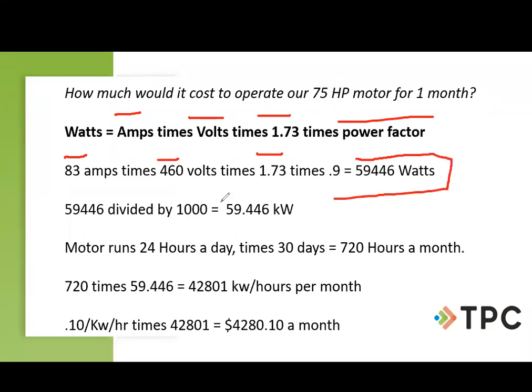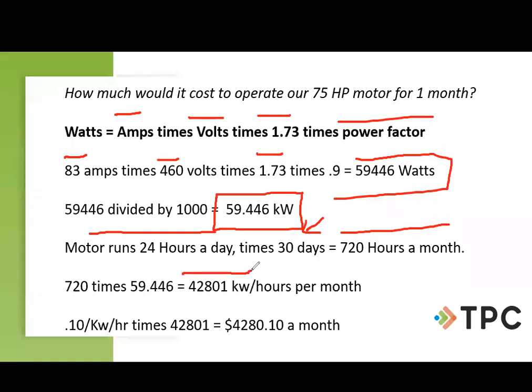All right, that's great. But we're going to divide it by 1,000 because the utility likes to charge us in kilowatt-hours. They're going to charge us for that. So if that motor runs 24 hours a day, let's say it's a month that has 30 days in it, that's 720 hours a month. All right. So 720 times our 59, which is our kW, gives us this many kilowatt-hours per month.